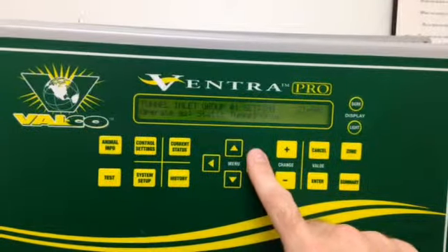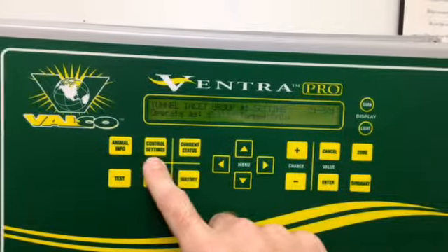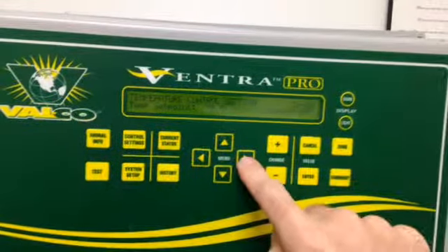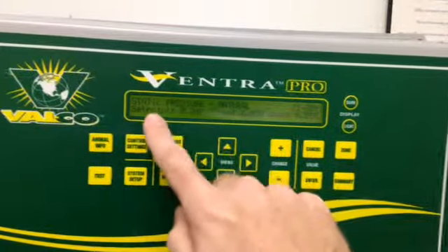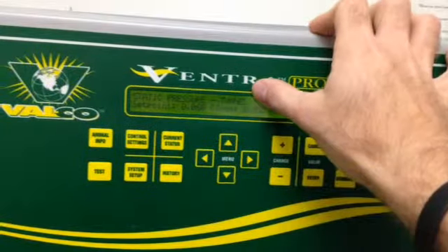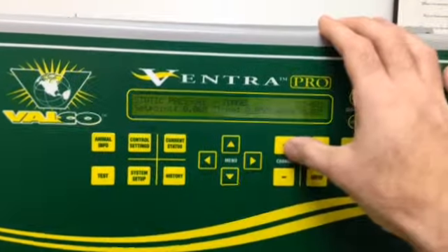The other setting that we would need to check on is what the set point is for where we're actually trying to achieve with our static pressure with our tunnel. That's found under the control settings hotkey. Starting from temperature control, we can move to the right until we find static pressure. You'll see that there's both natural and, if you arrow down, tunnel.